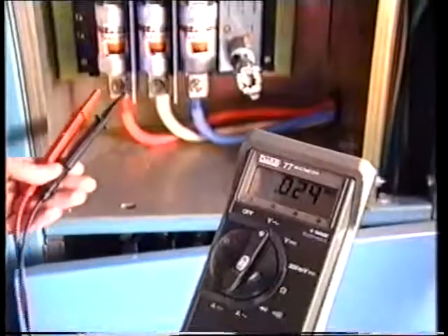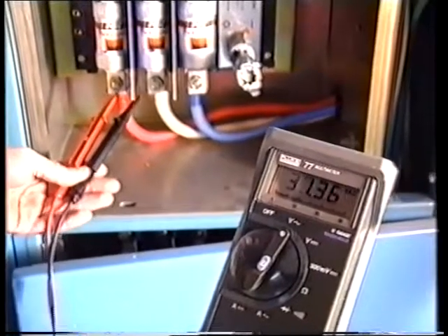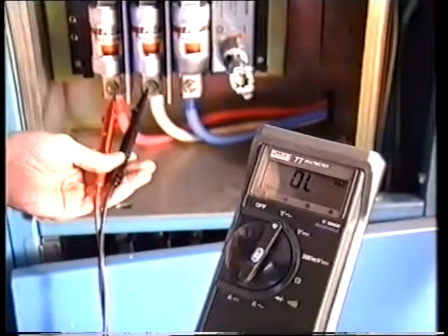Electricians may have a requirement to work on the input AC power circuits, but it is not necessary to shut the complete unit down for this purpose. In this case, the AC isolation procedure should be carried out. Now to the shutdown procedure in detail.